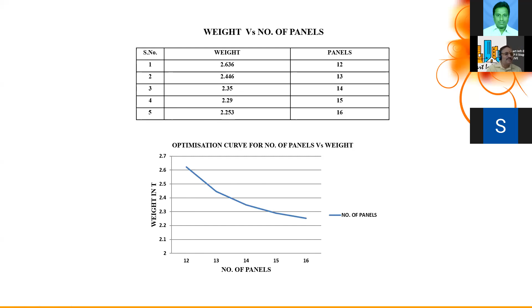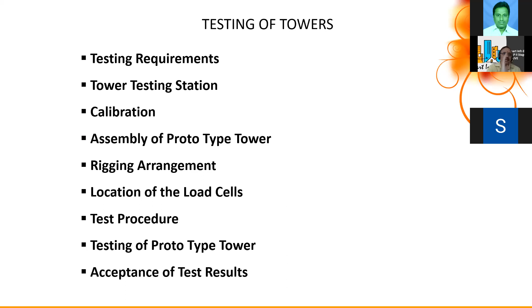So testing of towers, we do, as I said, prototype testing of these towers, and calibration of the testing station, assembly of prototype tower, rigging arrangement, rigging chart we call, for loading calibration. Every tower testing station will have a different rigging arrangement. And so we verify the rigging chart to check whether the loads considered in the design are being applied in the real testing station.